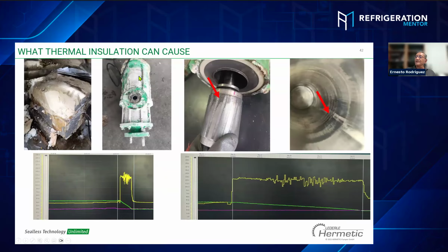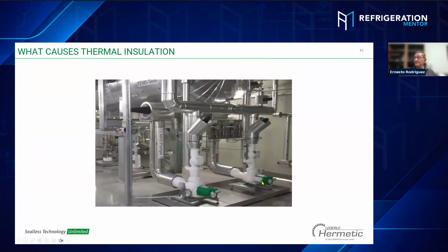Why? Because the heat generated by the motor is going to stay in with the insulation and it's going to build flash gas inside the pump. CO2 is more critical versus ammonia. And we have a sample right here. This is a CO2 pump that was insulated, and at some point they called me that the pump was damaged, and I said okay, this is the problem. The best way to run the pump is with no insulation. The ice is going to help cool the refrigerant and cool the motor. That is the best way.